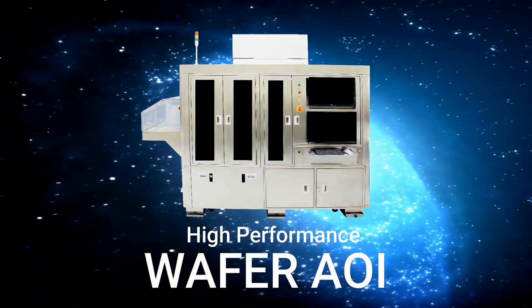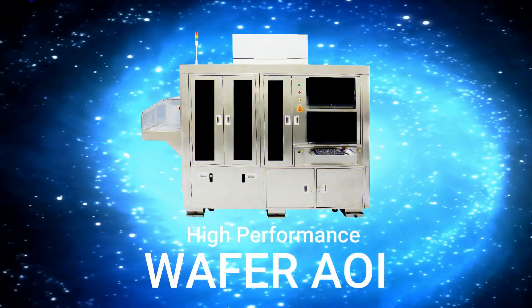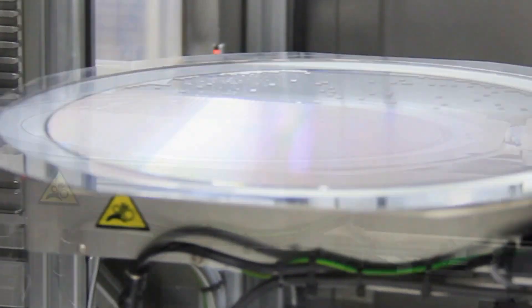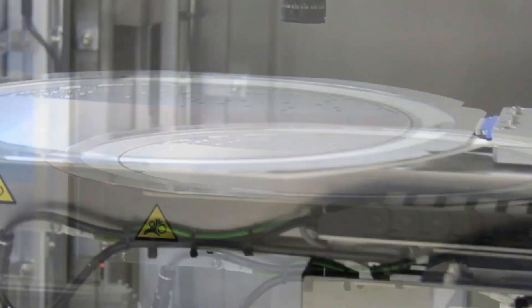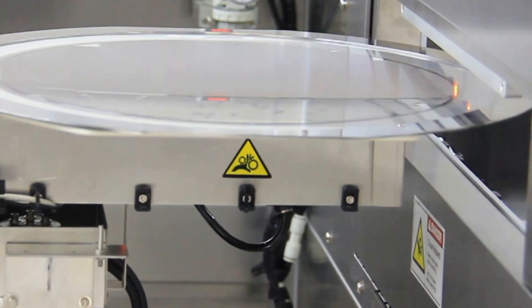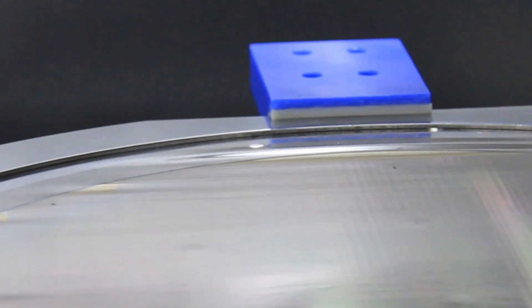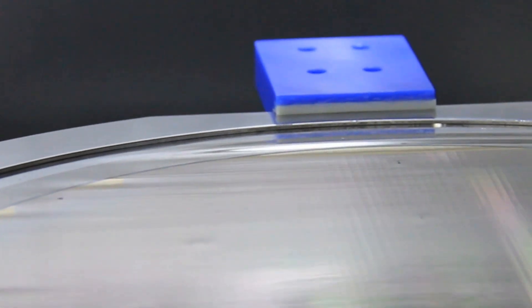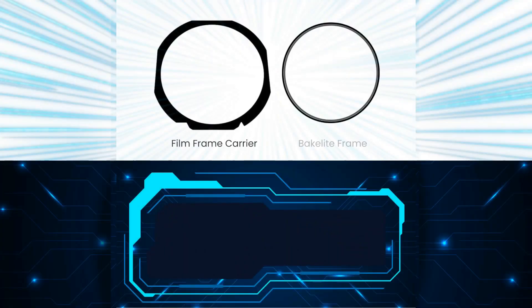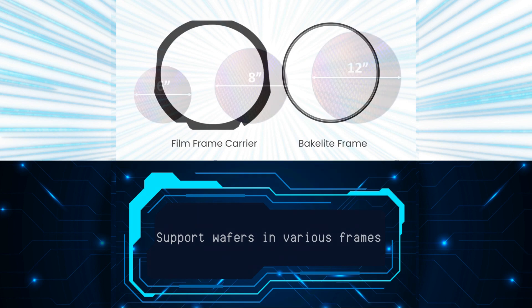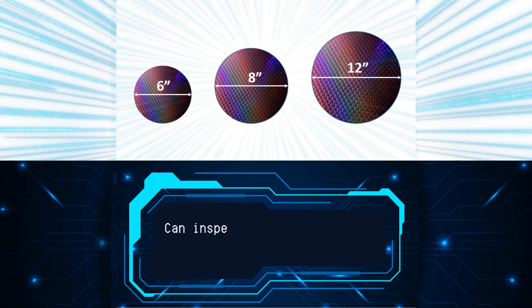Cortex Wafer AOI is a high-performance wafer inspection solution designed to inspect major or minor wafer defects after the sawing process. It supports wafers in various frames, for example film frame carrier and bakelite frame, and can inspect up to three different sizes of wafers.